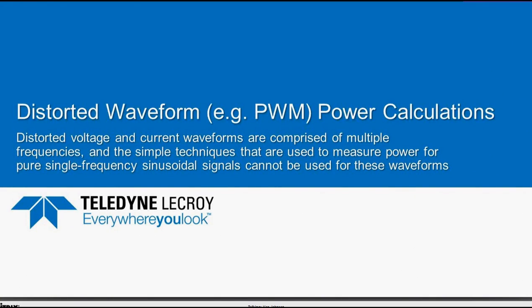Okay, now we're going to talk about distorted waveforms. Realistically, even the nice sine waves coming out of your wall socket, as you saw on that previous screen image, can have distortion on them. So realistically, all waveforms are distorted. There are no pure sine waves developed, generated and delivered by the utility. But when you get into pulse width modulated waveforms, like on the output of an inverter or a drive, they can get really distorted. By definition, they're highly distorted signals. So let's talk about that.